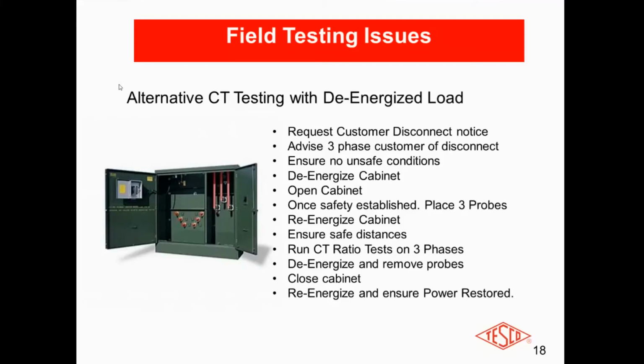We got into quite an interesting conversation about this, and even between utilities, about whether this is even practical. It is possible, but I really don't think any large three-phase customers would relish the idea of having their production lines shut down and then re-energized and then de-energized again. That's 4 sequences that they're going to have within an hour. So I'm not sure about controlled outages like that, although they are controlled and they're safe and very little should happen, you're also energizing the switchgear, you're energizing everything else in there. So from a maintenance and service standpoint, that could be a problem. It's certainly true that personnel are not at risk. There's definitely a positive there as well. So it's a difficult one to decide.